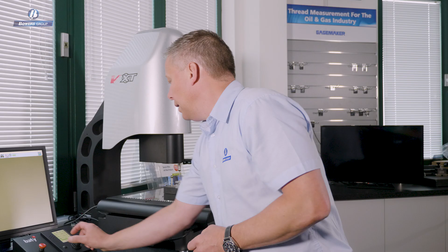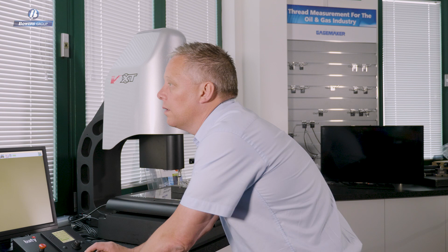And now I'm going to change tip, and we'll select one of the X-axis tips and measure some features on this face. So next let's measure a line. I'm going to use a different tip to do this because I want to use a line on the side of this component, so I'm just going to use the graphic I referred to earlier. Let's click on the X-axis stylus and just drive down. I'm going to measure a line, so let's come somewhere close, call up for a line measurement, and again just flick the joystick towards the part, and the part is measured using controlled probing speed. So again, I'm not influencing that measurement. So that aligns the part, and now let's measure some other features on this side face. Let's call for a plane, and we'll first of all measure the plane around this bore.